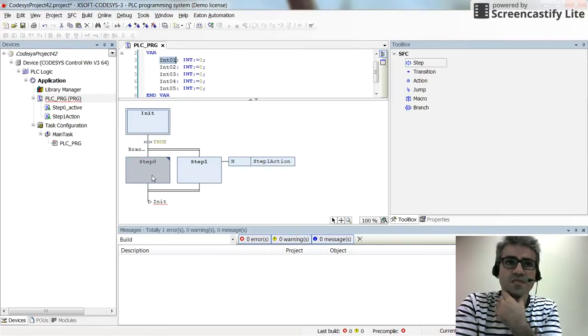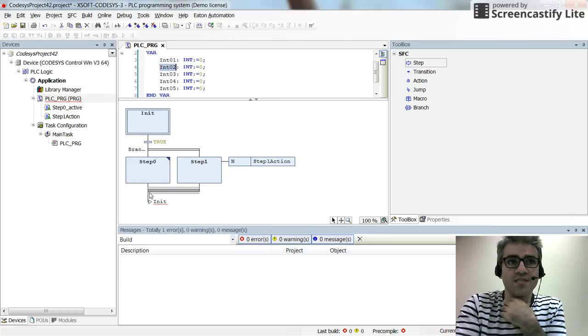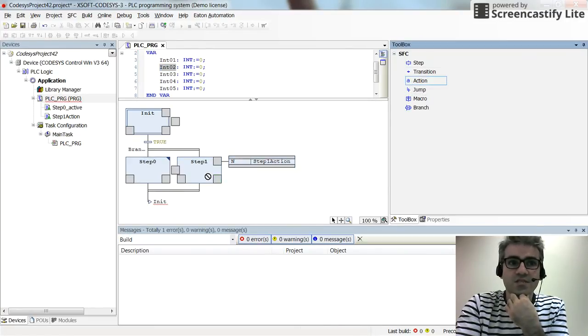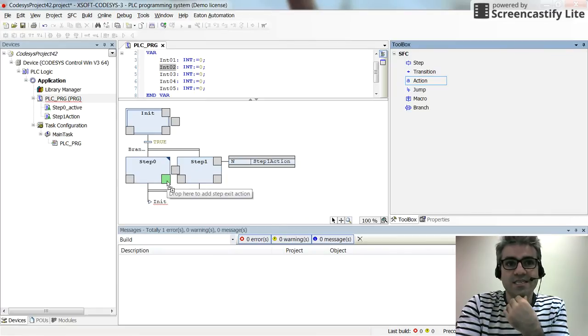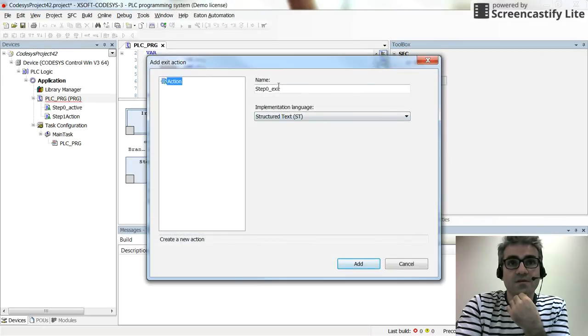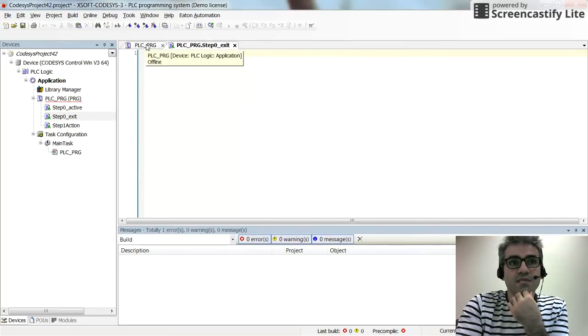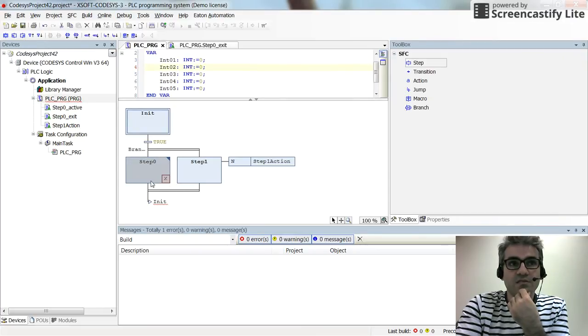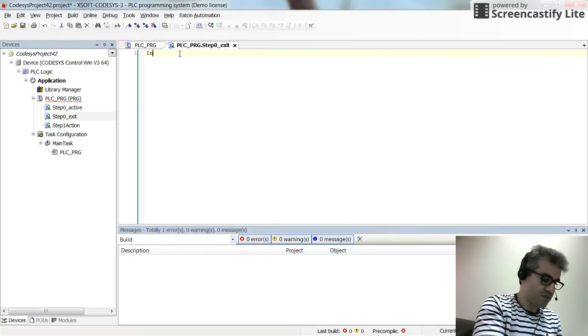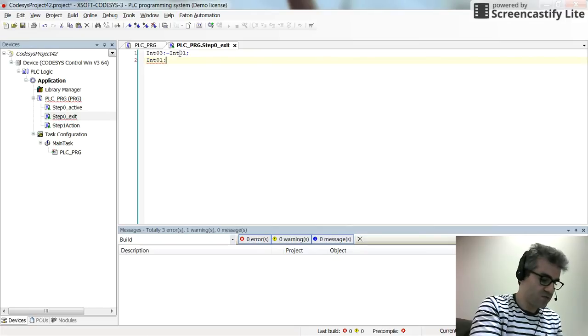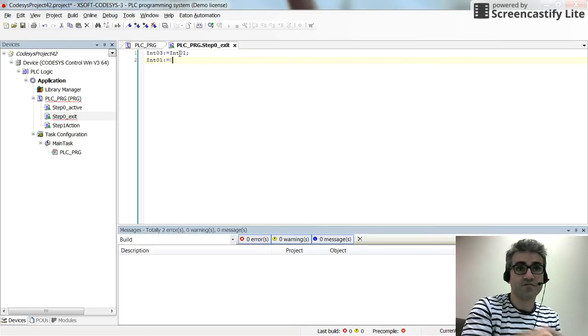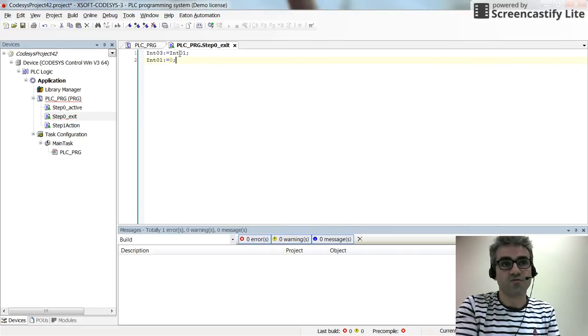Furthermore, I want to keep track of the value of int01 and int02 at the end of the steps. For that I am going to introduce another action for the step exit. Again, structure text as the programming language. Here I want to put the value of int01 into int03 and then reset int01 to 0. So int03 equals int01, then int01 is set back to 0 — otherwise int01 will keep increasing as execution continues.